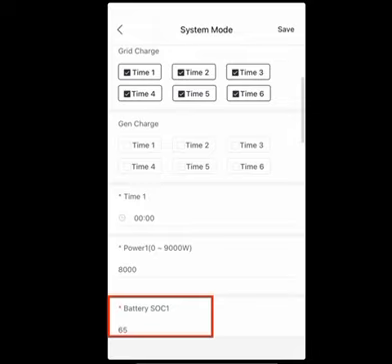During load shedding or power outages, the batteries will discharge below the set state of charge, to the minimum shutdown percentage selected, normally 20%. When the grid again becomes available, the batteries will be recharged back to the set state of charge, for example, 65%. It will be further charged to 100% when solar power becomes available.